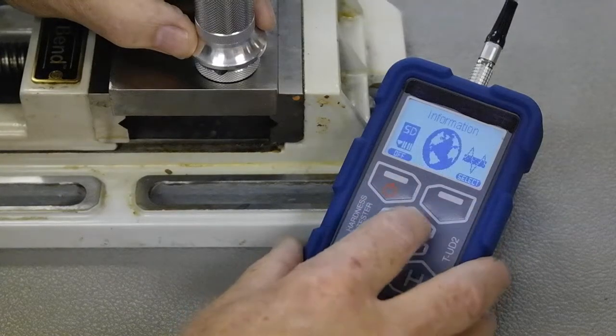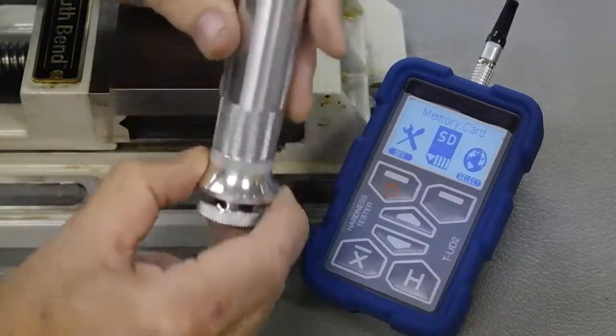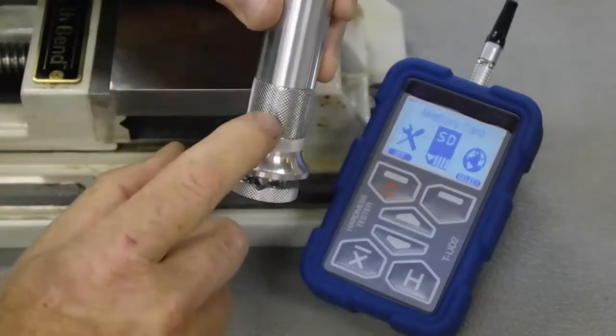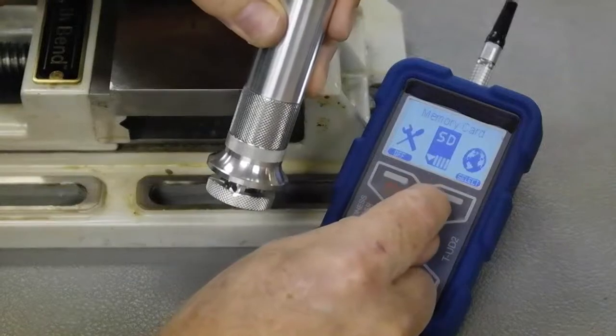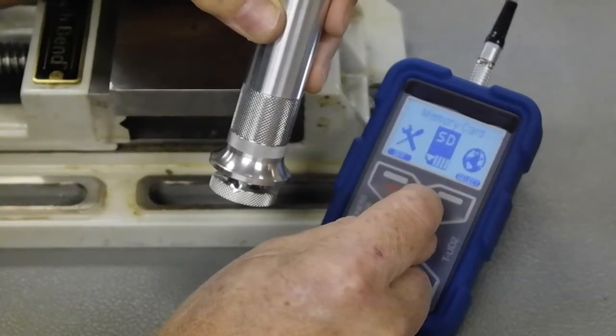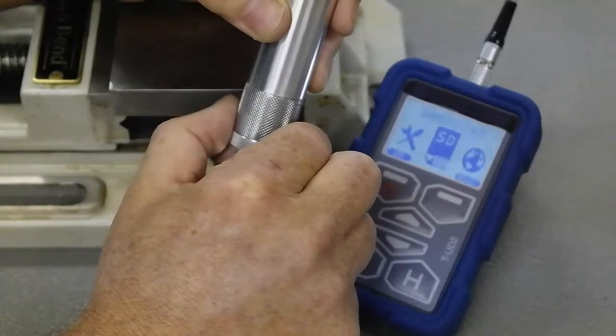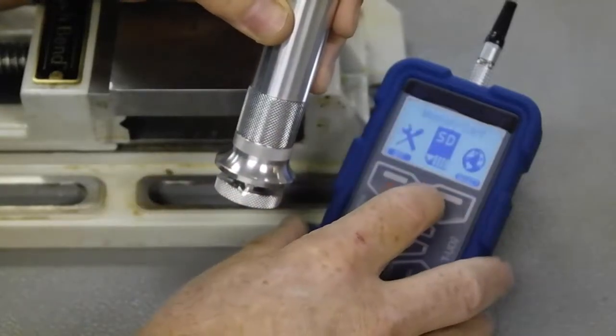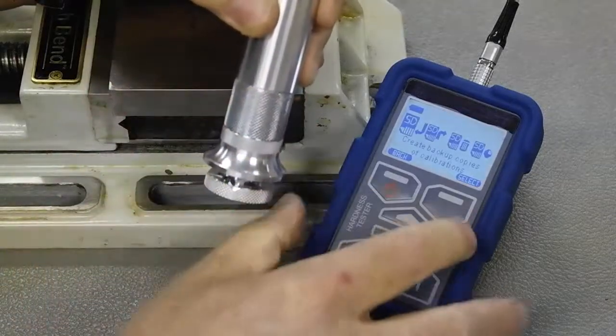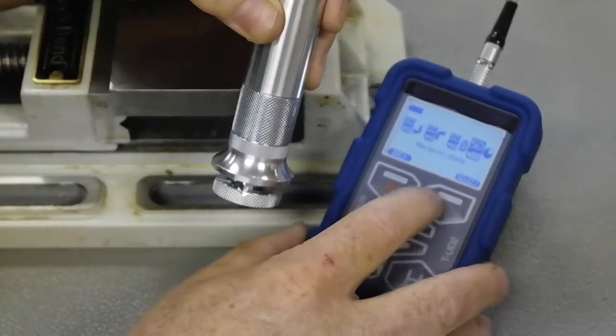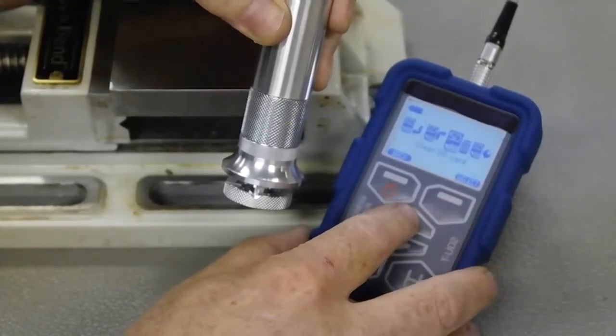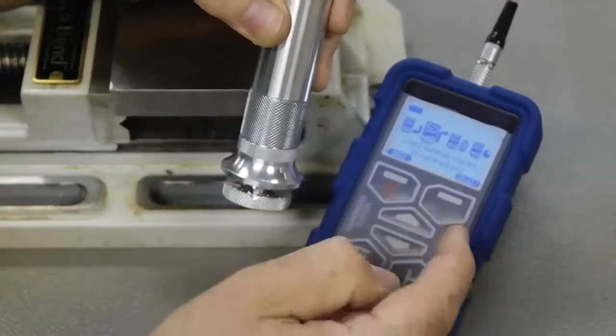So just go back. Memory card — as I said, the device itself has its own memory, but if we want to copy from the device back to here for archival reasons, or perhaps before doing a recalibration in case we make a mistake, we can always recall from here back to here and vice versa. If I go into this, you can see I can create backup copies of all the calibration, check the memory state of the little card inside, clear it, and load the backups back to the device if I make a mistake and don't calibrate correctly.